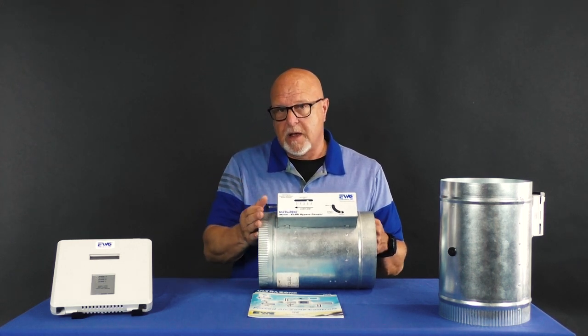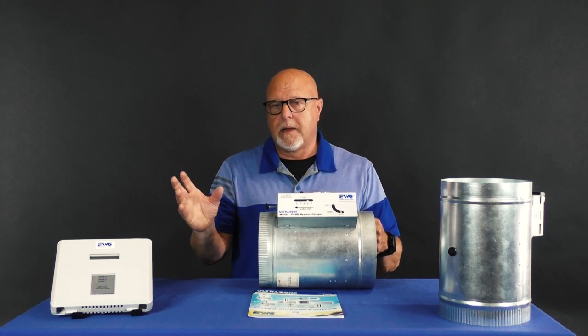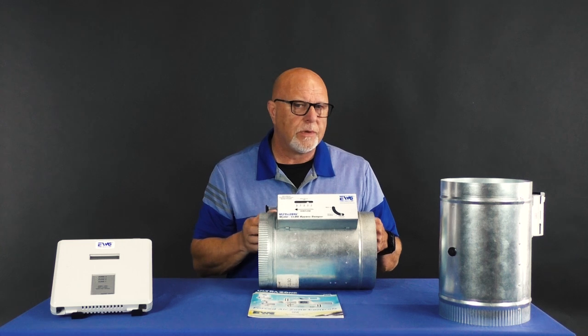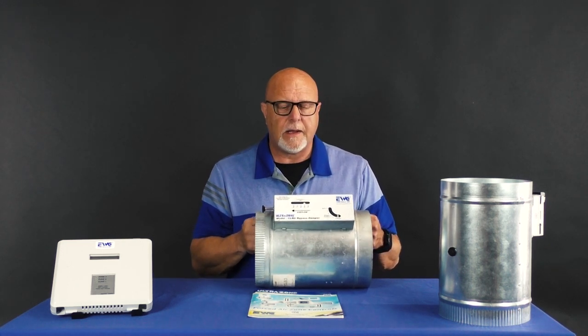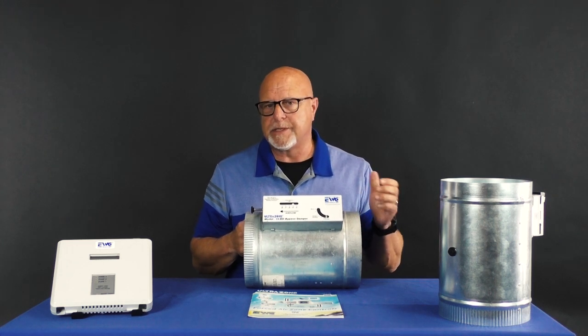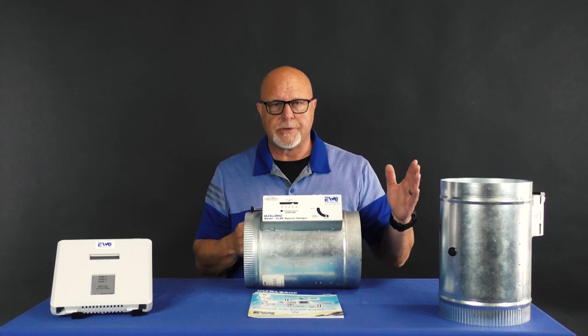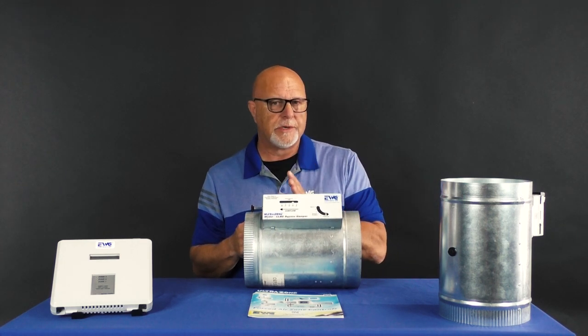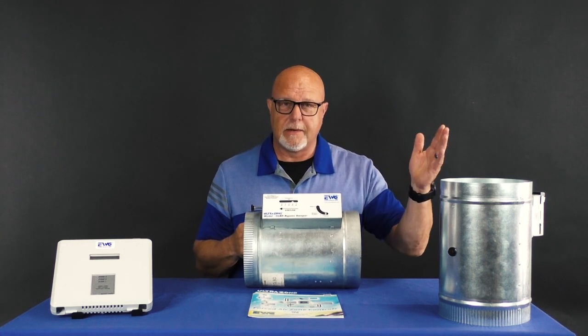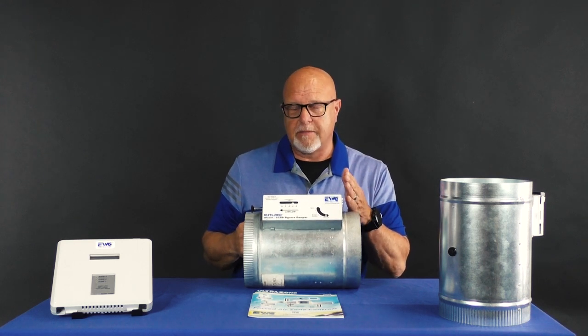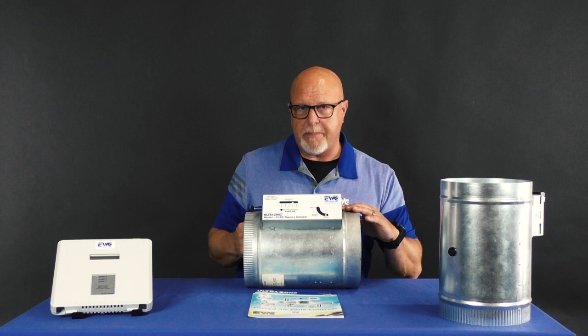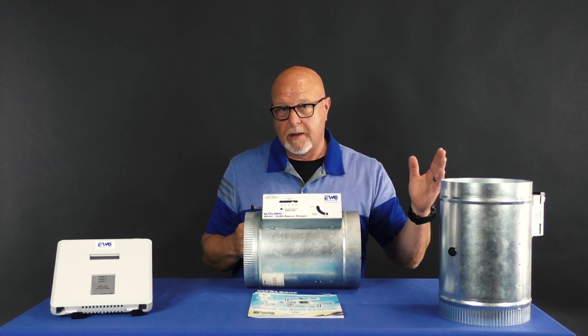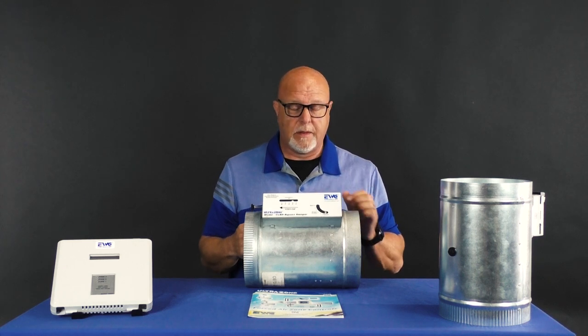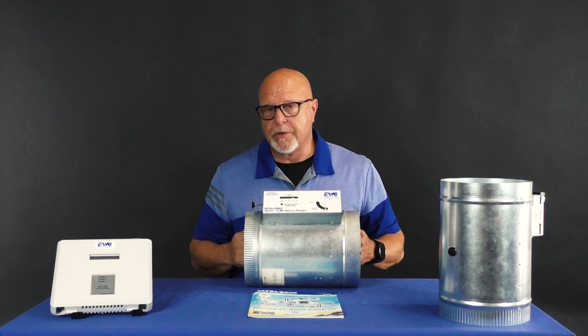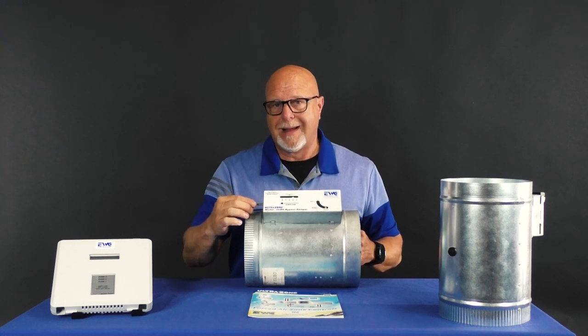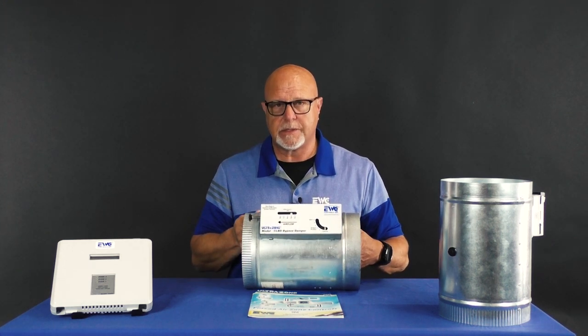So you're going to obviously make a bypass loop coming out of the supply and bringing that loop back into the return. And we want to tie that into the return far enough upstream of the equipment to allow that air to mix and moderate with the return air coming back into the system, allowing that bypass air to warm up or cool down depending on what the operation of the system is. Once you have that installed, with a simple turn of a screw, you can set the static pressure at which you want this damper to open and close.